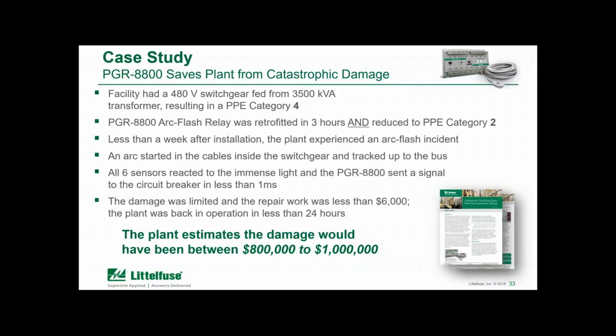Now they decided to retrofit an arc flash relay into the switchgear, and the install took only 3 hours, and that resulted in the PPE category dropping down to category 2. And as it turned out, just less than a week after that installation, the plant did experience an arc flash event, and in that event, the arc started and the switchgear cables tracked up the bus. And in looking at the analysis, all 6 of the light sensors did react to the light from the arc flash, and the relay sent the trip signal as expected.